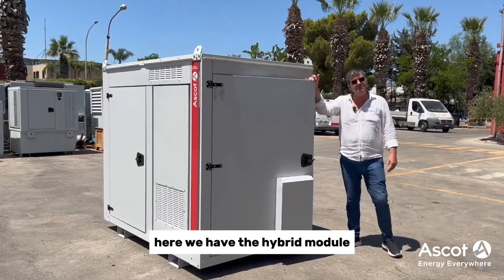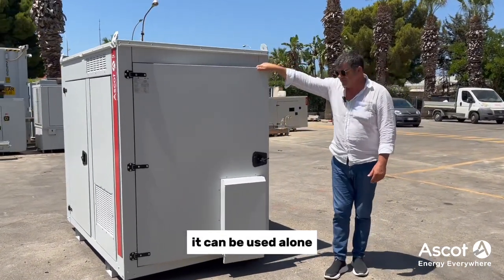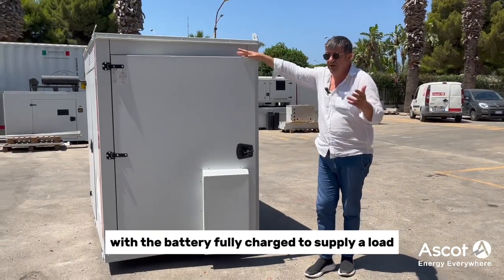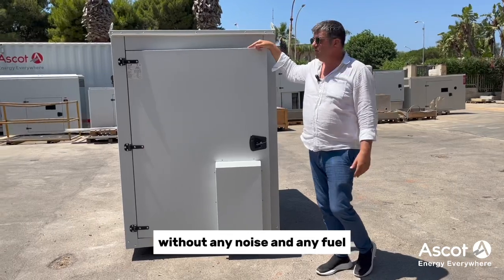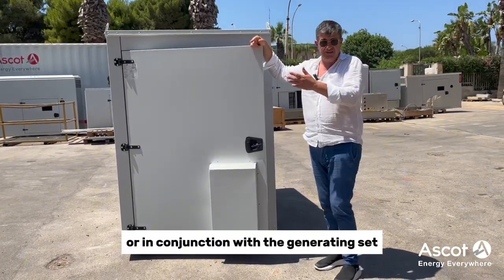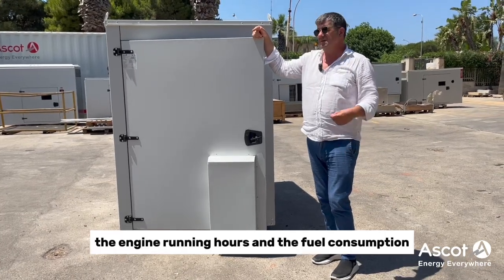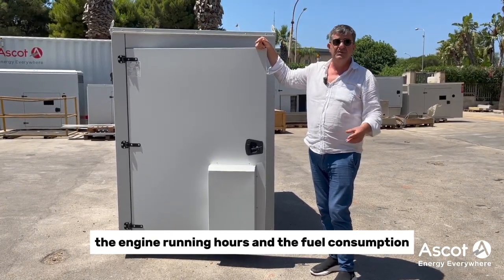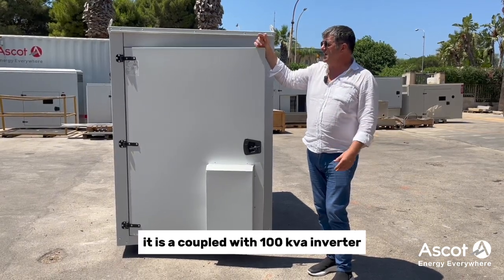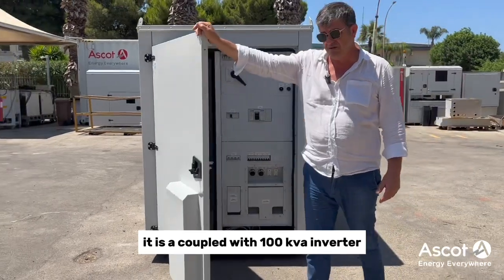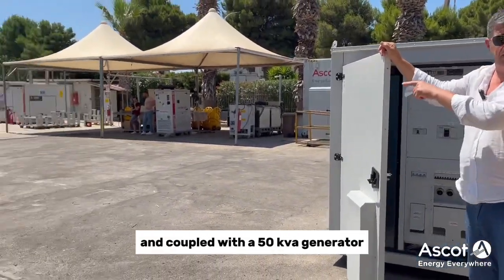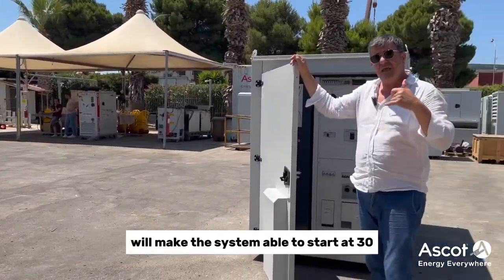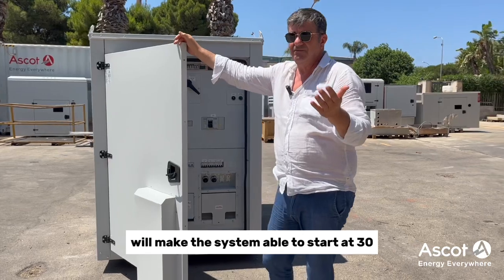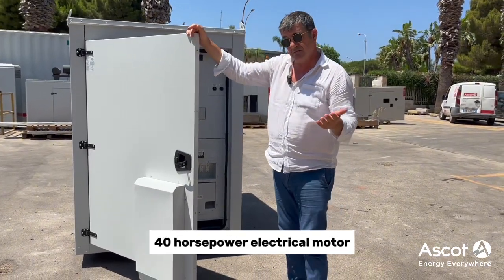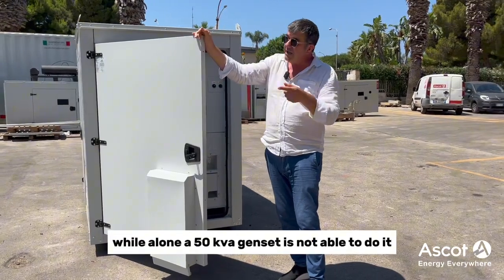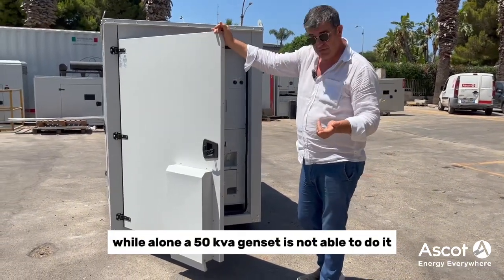Here we have the hybrid module. It can be used alone with the battery fully charged to supply a load without any noise and any fuel, or in conjunction with the generating set to reduce the engine running hours and the fuel consumption in some conditions. It is equipped with a 100 kVA inverter and, coupled with a 50 kVA generator, will make the system able to start a 30-40 horsepower electrical motor, while alone a 50 kVA genset is not able to do it.